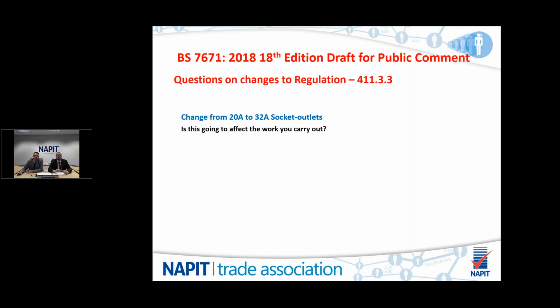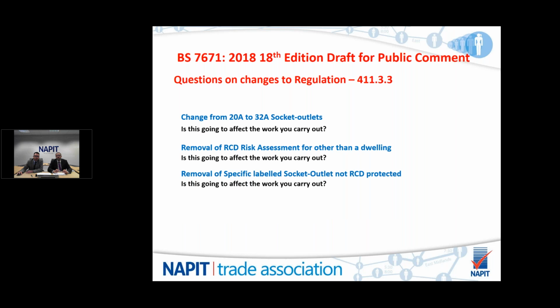So, first one. We change from 20 amps to 32 amp socket outlets. Ask yourself if that's going to affect the things that you do for your industry. Because if it does, you need to comment. And second one, the removal of the RCD risk assessments other than a dwelling. In your business, did you do a lot of that? Did you carry out risk assessments for other than dwellings? Does it form a large part of what you do? And will this change affect that? The removal of specific labelled socket outlets not RCD protected. In your business, your day-to-day work, is this an area that you deal with, that you've had to do, that affects you? Will this new regulation affect you? If it does, make a proposal.